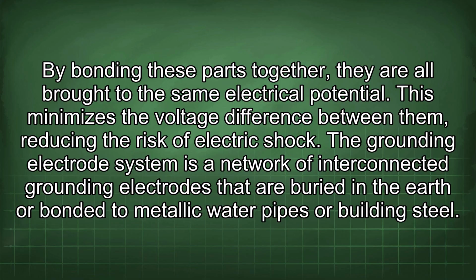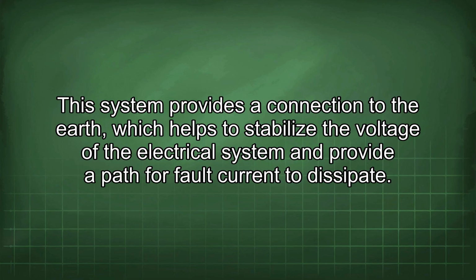The grounding electrode system is a network of interconnected grounding electrodes that are buried in the earth or bonded to metallic water pipes or building steel. This system provides a connection to the earth, which helps to stabilize the voltage of the electrical system and provide a path for fault current to dissipate.